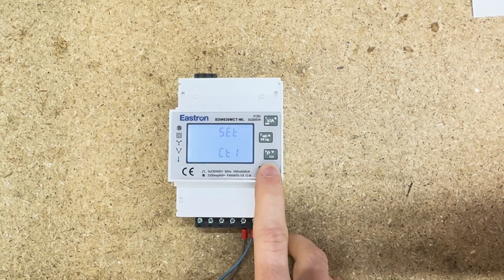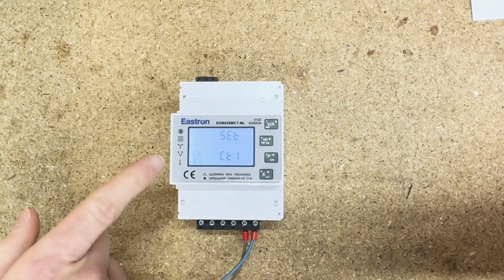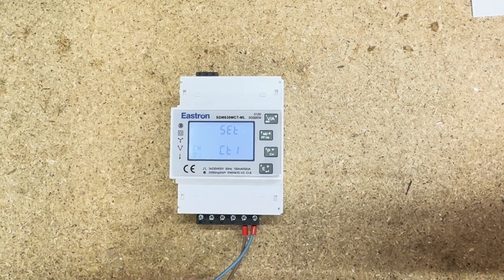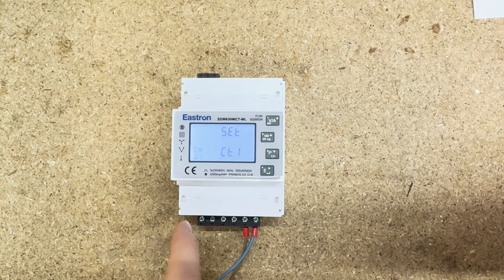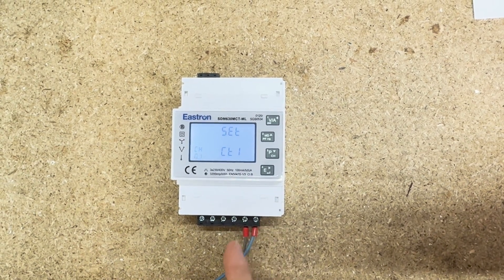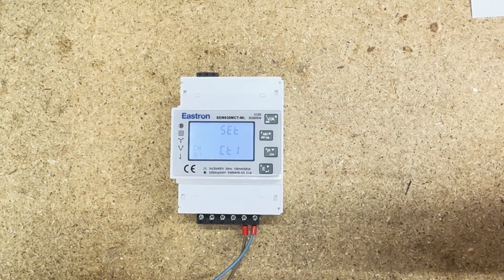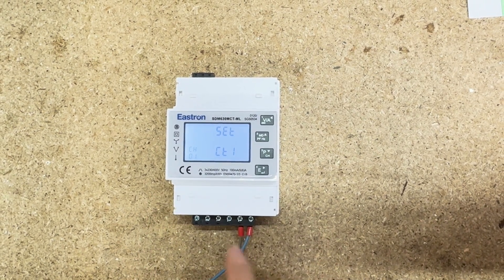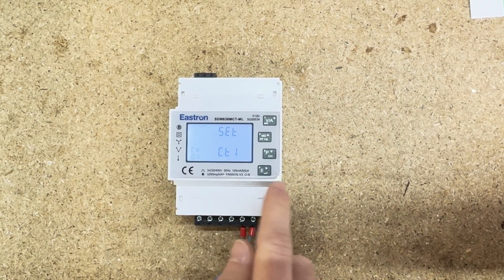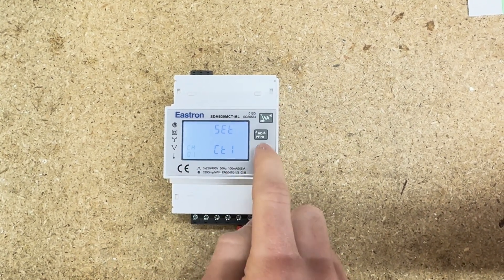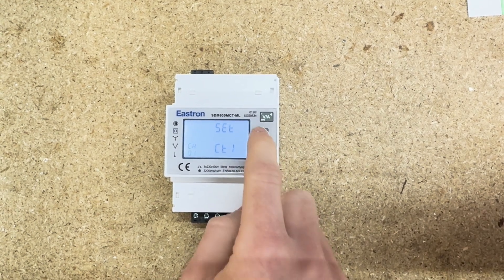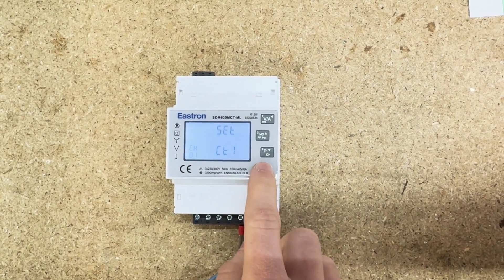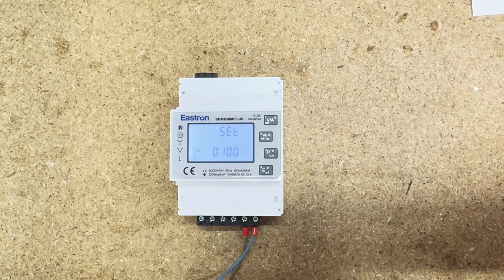CT2 we don't want to mess with because it's always going to be 100 milliamp for these meters. For CT1, we press and hold E and now we get to choose the channel — whether it's channel 1, channel 2, or channel 3. That refers to the loads you're monitoring, because with these ML meters you can monitor up to three loads with a single meter. This is a 1L so we're only monitoring one load, meaning it's just channel 1. We'll press and hold E to lock in channel 1.